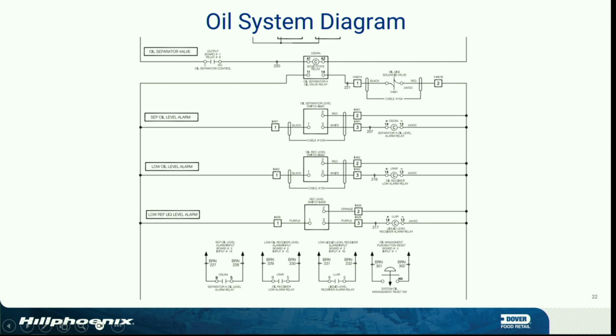All right, so this is our standard oil separator. We're going to go over the oil separator because the one thing I want to do when I leave the job site is that you guys know how the oil system works. I don't want to get a call 2 months later saying, hey, I replaced the HV sensor 3 times and the system's still not working. So what we have in our system is a lot of components. You've got your 24-volt oil sensor, right? 24 volts. When we detect a liquid, the switch makes.